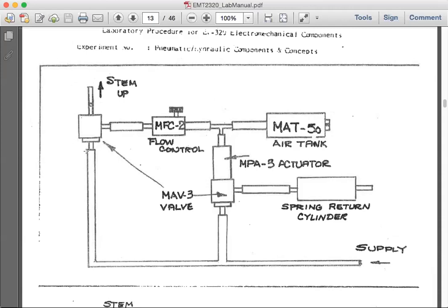Then you block the pressure coming from the bottom of the valve, and the pressure that right now is in this part of the system, because the stem is up, it's venting from the right side into the hole in the stem of the three-way valve. Okay, so right now this line is blue because the stem is already released, so air without an obstruction comes right here and vents blue from the hole in the stem.